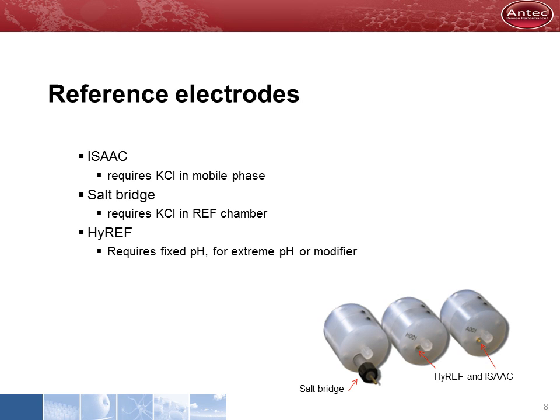This photo shows how three different reference electrodes look. As a standard, we use the ISAAC. Only in case of extreme conditions such as a high pH or high modifier percentage, we use the HyREF. The salt bridge is used in cases where both others cannot be used, for example when chloride cannot be added to the mobile phase.